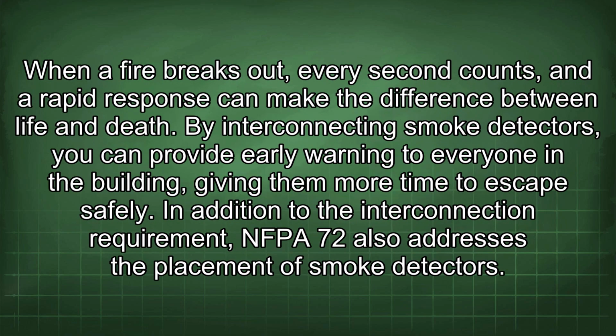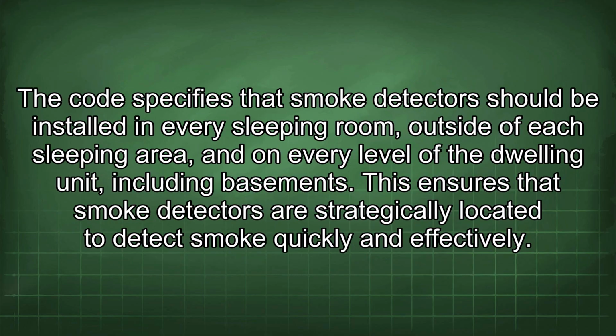When a fire breaks out, every second counts, and a rapid response can make the difference between life and death. By interconnecting smoke detectors, you can provide early warning to everyone in the building, giving them more time to escape safely. In addition to the interconnection requirement, NFPA 72 also addresses the placement of smoke detectors. The code specifies that smoke detectors should be installed in every sleeping room, outside of each sleeping area, and on every level of the dwelling unit, including basements.